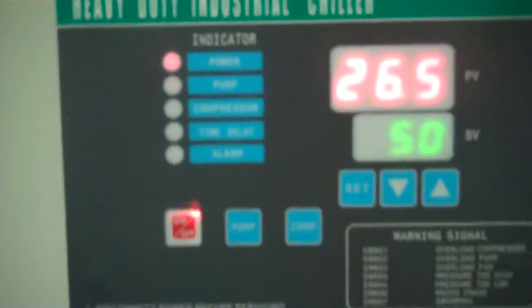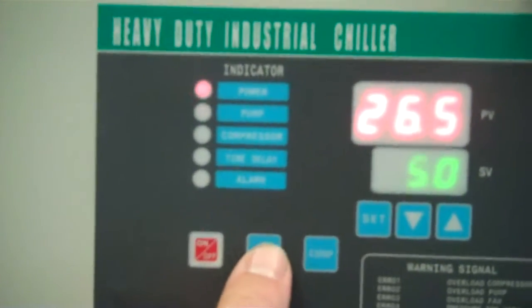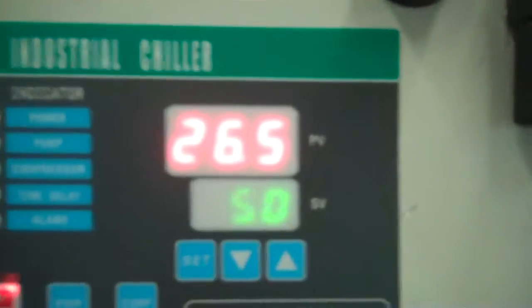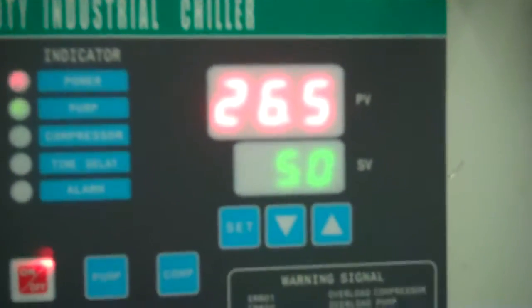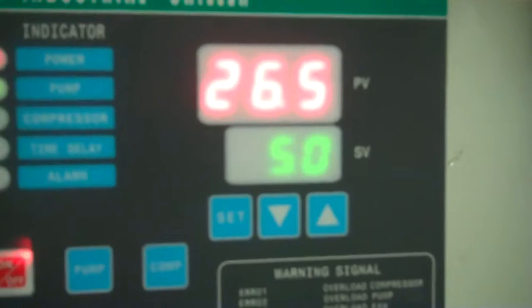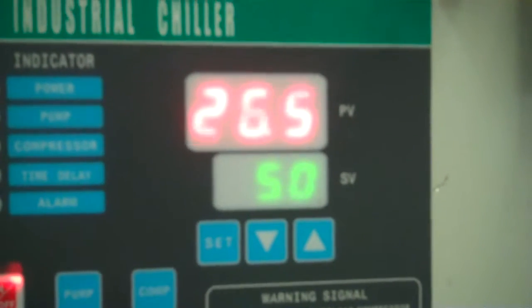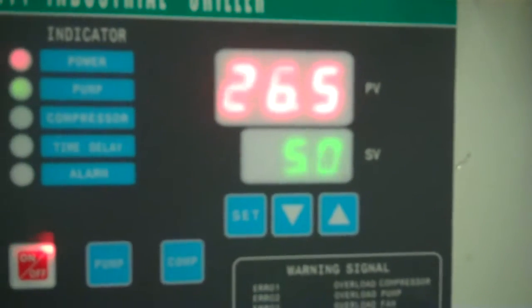We've tested it thoroughly and ran it for quite some time already. These are 460 volt, 3-phase units. This one we already have the power on, and we're simply going to turn the pump on first. We already have the set point set at 5 degrees centigrade. Right now we have the water heated up to a little bit over 26 degrees centigrade, so the water is about 80 degrees, give or take.